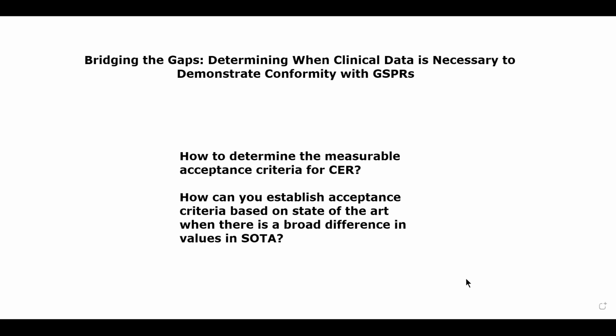So let's say that your device has a particular safety event, bleeding. And if the bleeding occurs between 1% and 5% of patients, then that range is going to be determined from that measurable outcome. That's something that's reported in the literature. You've conducted a search of the literature. You've identified articles that report on bleeding events. You summarize all of these articles, and then you have established that range of 1% to 5%. Your acceptance criteria would state that for a safety objective, you want to be below that top end. So your device should be no more than that 5%.